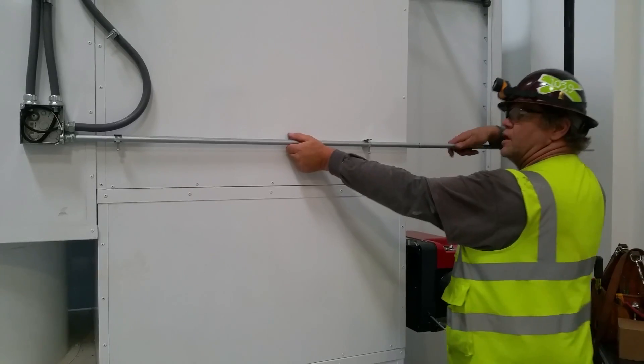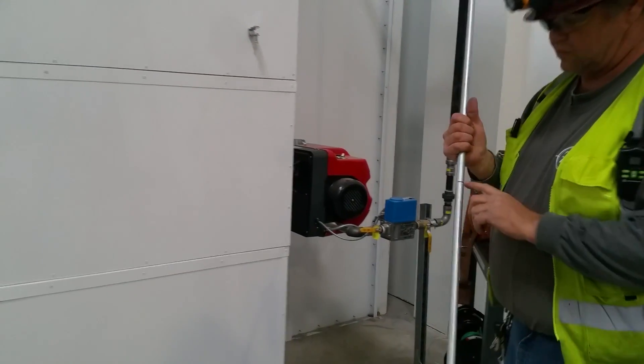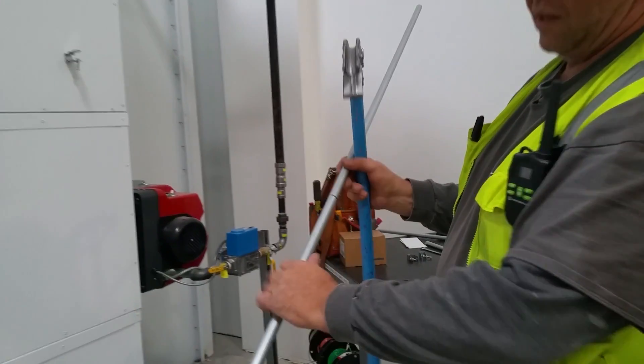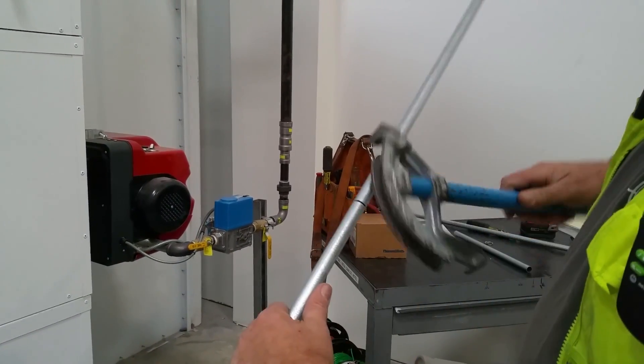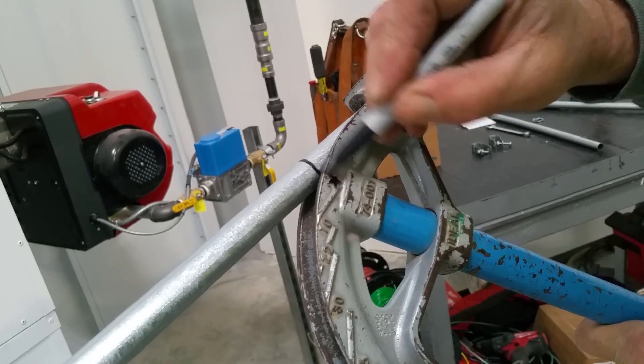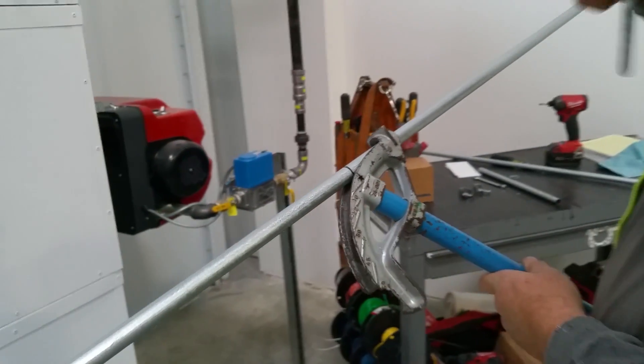If you recall from some of my other videos, we talked about back-to-back bends. We're going to grab our ideal bender and essentially we measured — even though we didn't use a measuring tape — we measured from this direction, so we're going to bend back towards that direction off of the star. Tip of the star right on the line — give it a quick bend.